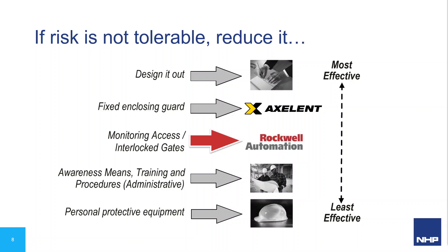The most obvious and most effective measure is to design your machine so it doesn't have the risk. But most of the time we don't have that luxury. So you can put in place some fixed guarding, which keeps people away from the hazard. But people need to access parts of the machine, so some guards should be removable — while monitoring whether the guard is in place so we can prevent dangerous actions when the guard is off.